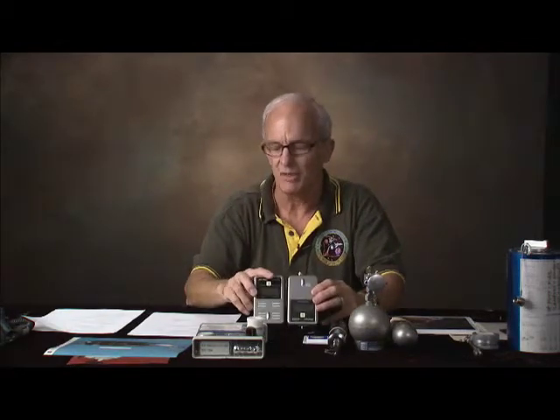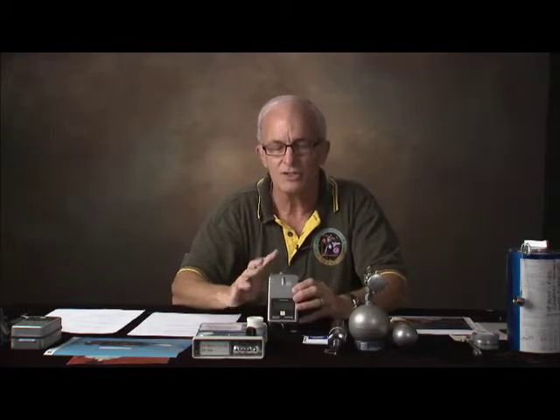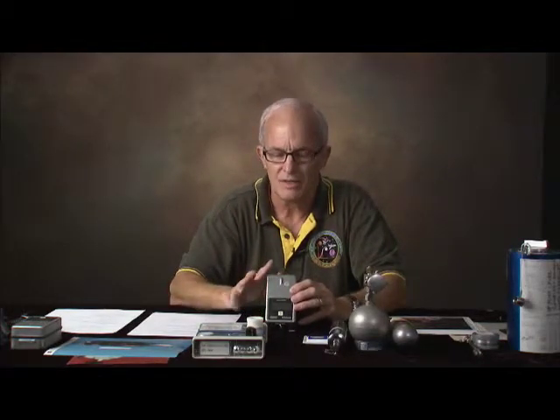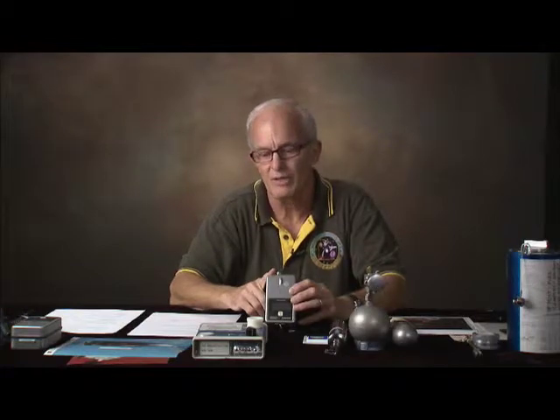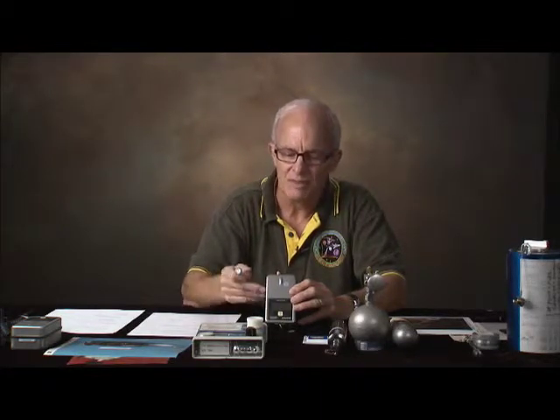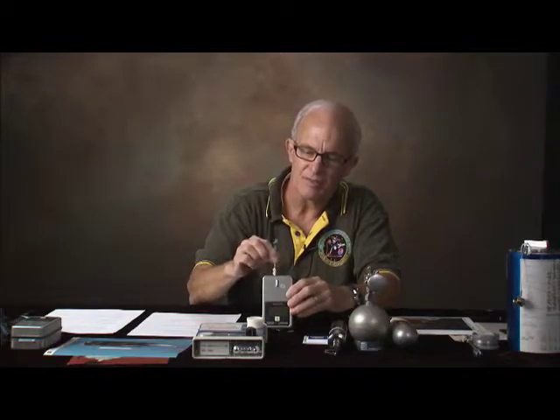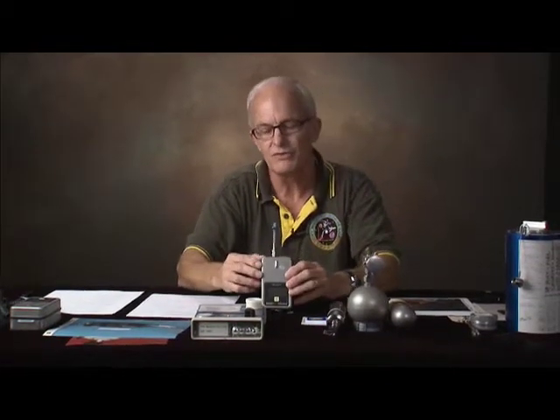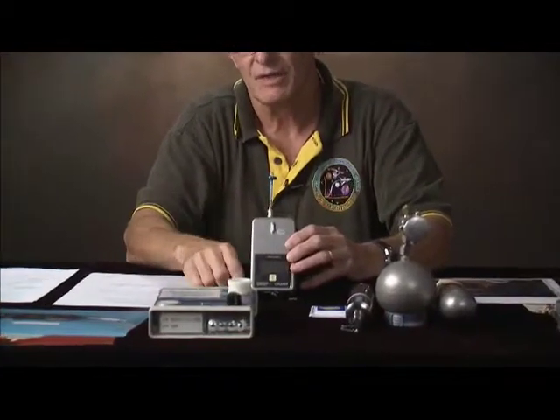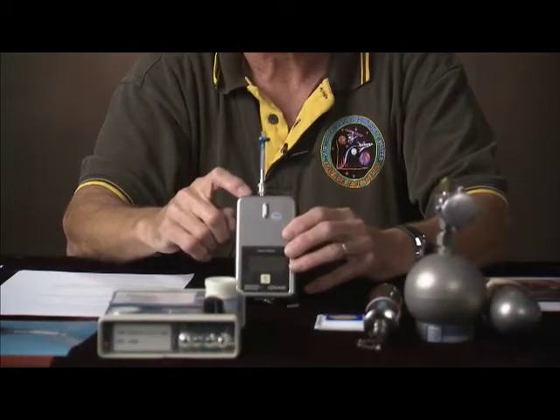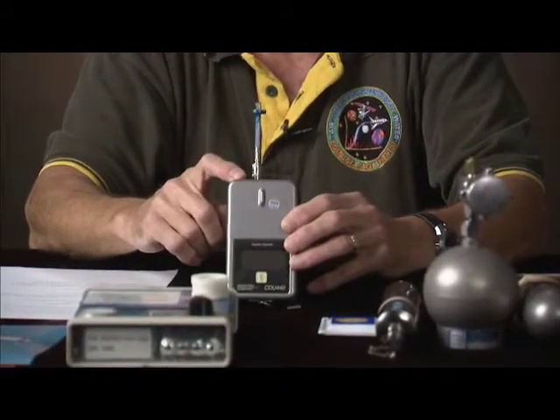It's built by the same company that builds ugly boxes for combustion products, as you can see, but this is a very different technology. This is infrared spectrometry, an exceptionally good instrument. I could throw this across the room, pick it up, and it would still be calibrated. We brought these things back, and even 400 or 500 days after they were calibrated, flown, and brought back, they still operate very well. The one thing needed is a little filter to remove water so that the tiny infrared cell in here isn't confused by the water being present.